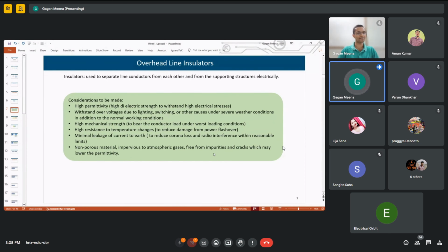Then they should have high mechanical strength because they have to bear the conductor load. The conductors are very heavy, especially at very high voltages, extra or ultra high voltages, and sometimes more than one conductor is used to reduce the reactance of the line. These are called bundled conductors. Because of the reduced reactance of the line, more power can be transmitted over the same line. There can be four conductors or six conductors in a bundle. Four conductors is very common; six conductors you can also find, but very few.